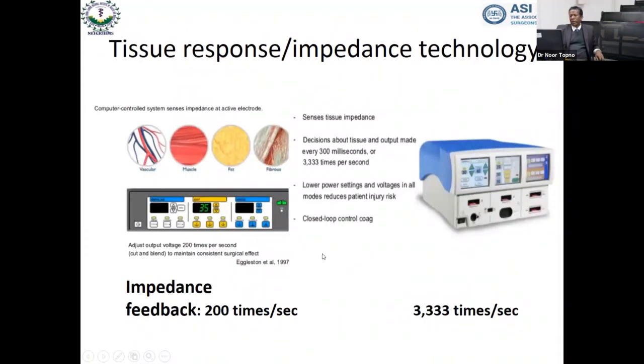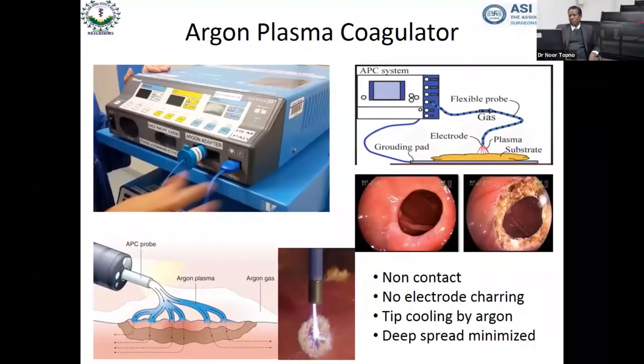Other thing is the tissue impedance, or the tissue response. In most older units, the electrode would give feedback to the generator as to how much the impedance is, and that used to happen about 200 times per second. The newer machines go up to almost as much as 3,000 times per second. Therefore, the machine decides at what point the current flow into the electrode will stop. And what it does is, by doing this, it automatically switches off the excess current. And that way, damage is much less.